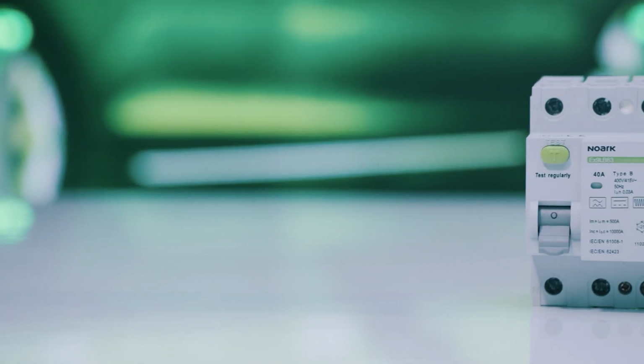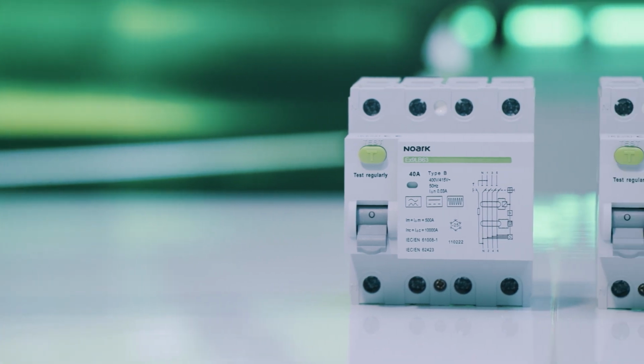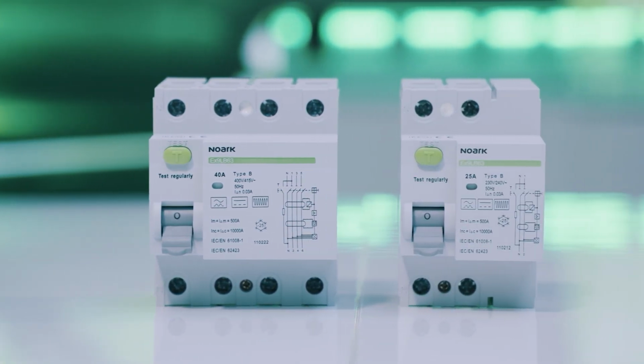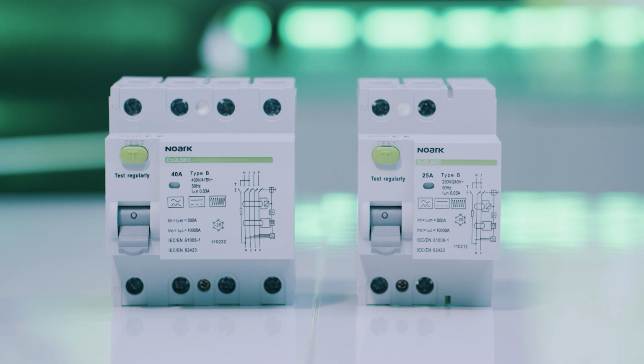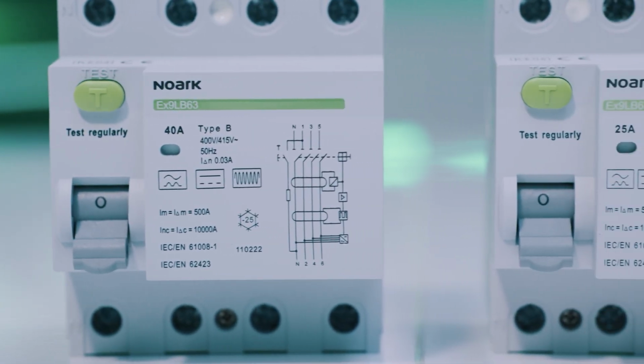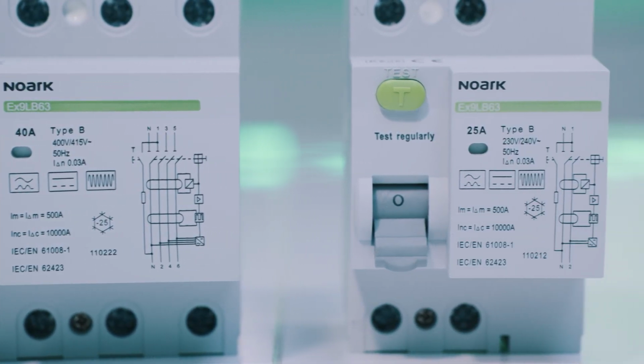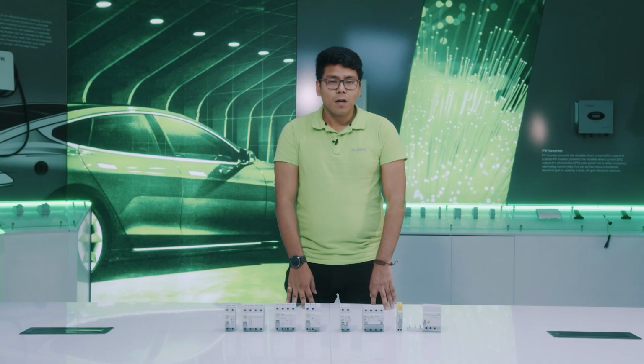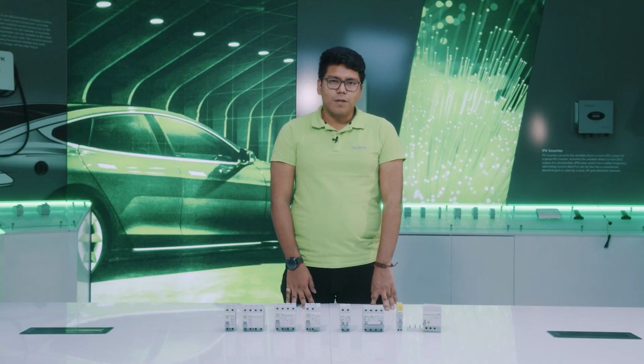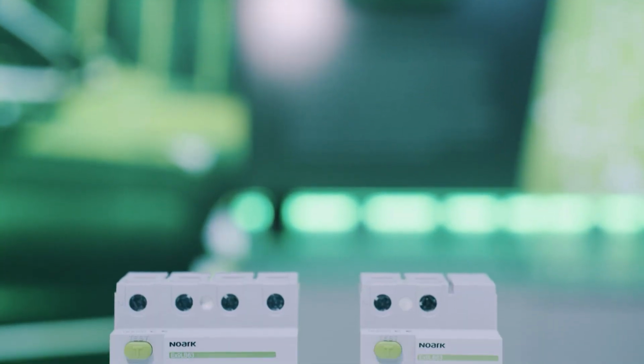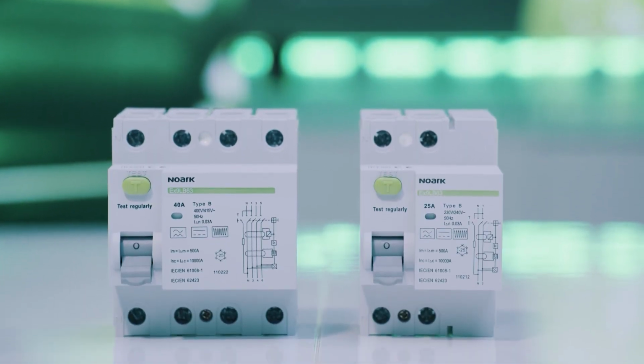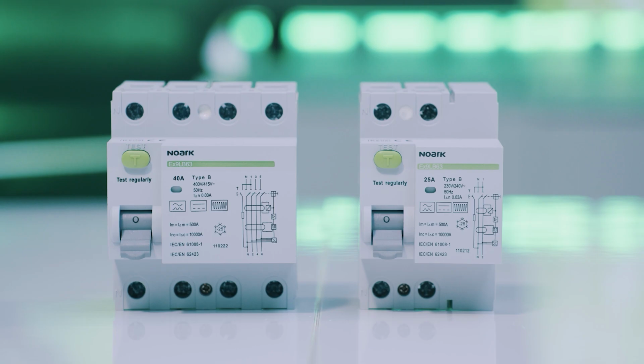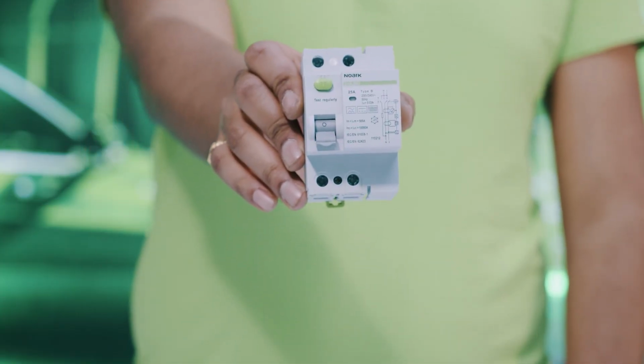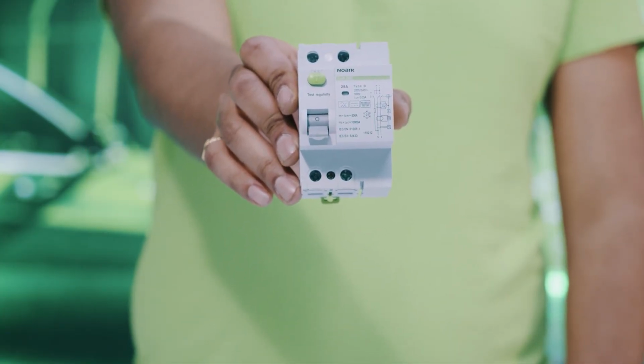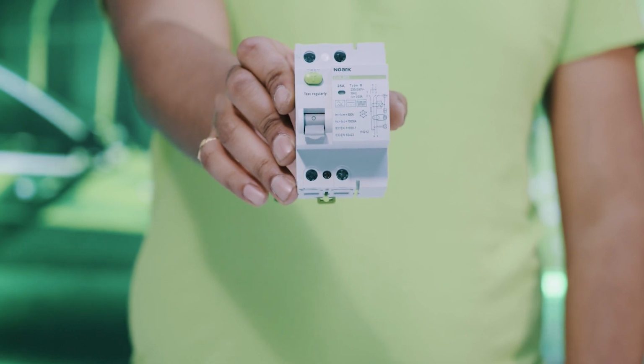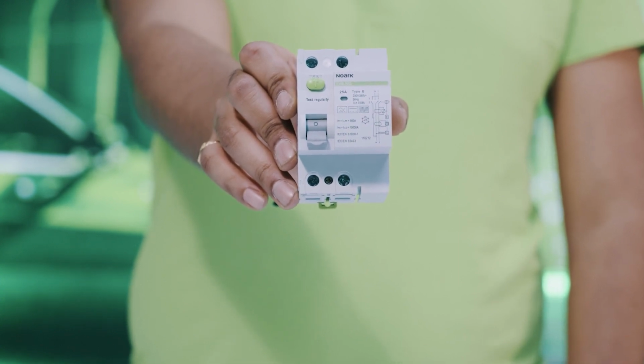Another type is the EX9LB63. It is a B type RCCB based on electronic technology, which brings the advantages of more accurate measurements of residual currents and, as a consequence, reduction of unwanted tripping. Also, internally it provides simultaneous protection by a type A voltage-independent RCCB. The nominal current range is from 25 amps up to 63 amps in 2 pole and 4 pole versions, with a sensitivity range of 30, 100 and 300 milliamps values of residual current.